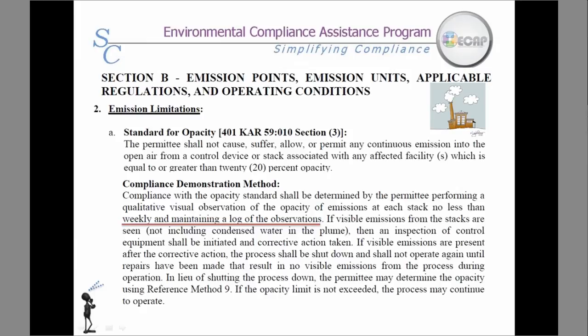Section 2 — emission limitations — is where you will find what the limitation is and how you are to prove that the limitation is being maintained. For example, a common limitation is an opacity limit or visual emissions limitation. The method of compliance for this unit is weekly observations and maintaining a log. Please note: if you are required to monitor it, then you should record it and it will need to be reported.